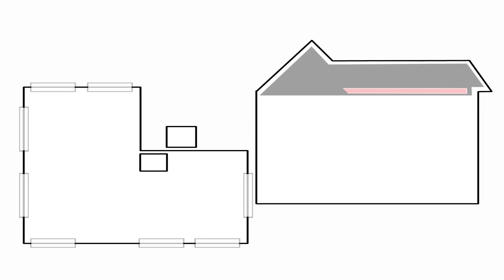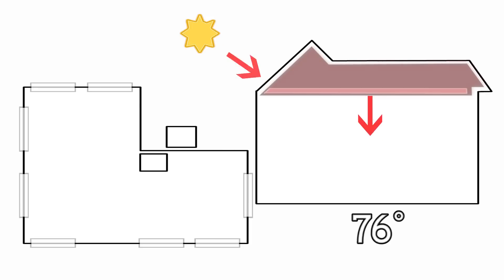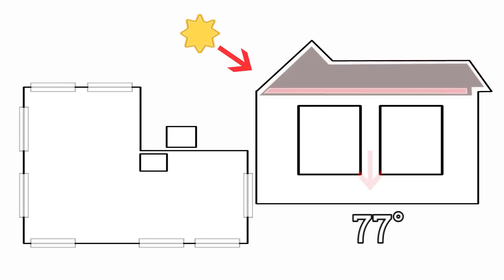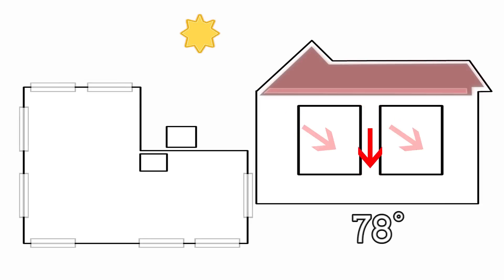On the 1600 square foot home, the insulation in the attic may be about 2 inches thick, but it's 140 degrees in the attic, and we're trying to keep it at 75 degrees in the home. Two inches of insulation in the attic may not be enough to prevent the hot attic air from entering the house. Now, add in the window sizes. If you have two large windows about 150 square feet in size, imagine the heat gain you'd receive on those two windows.